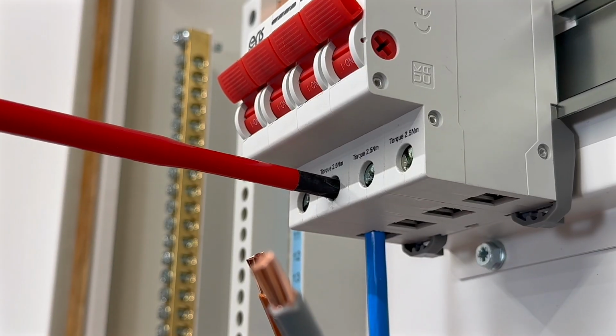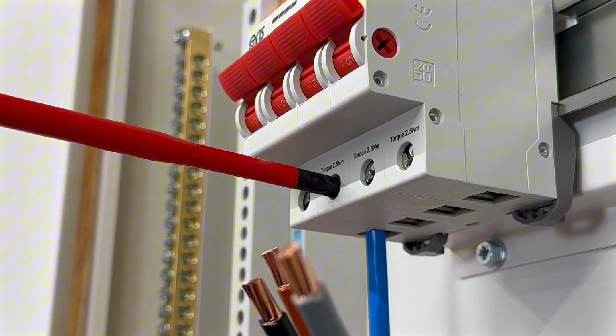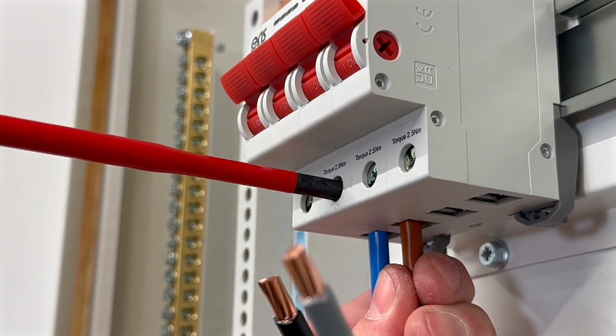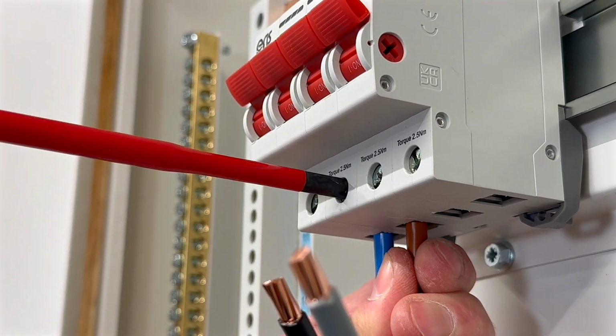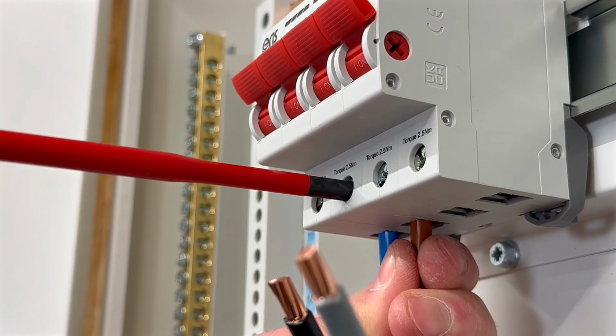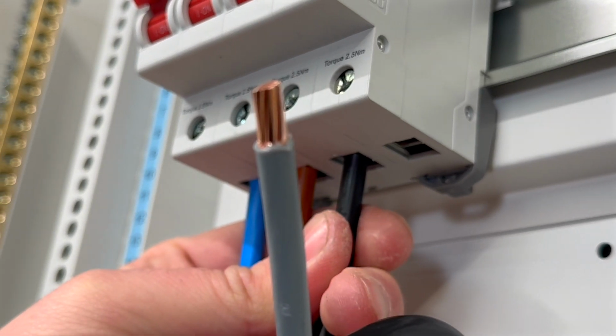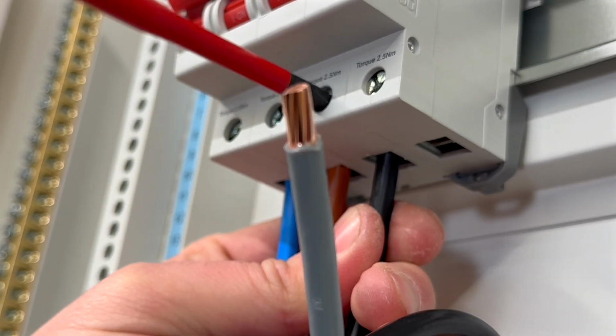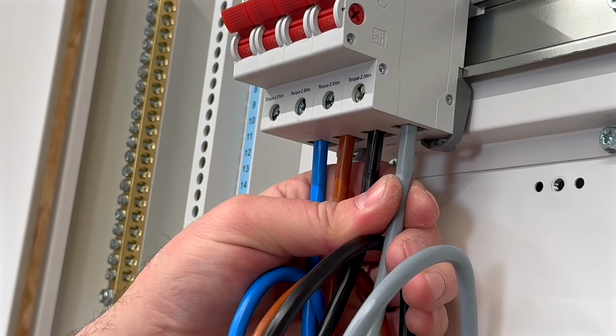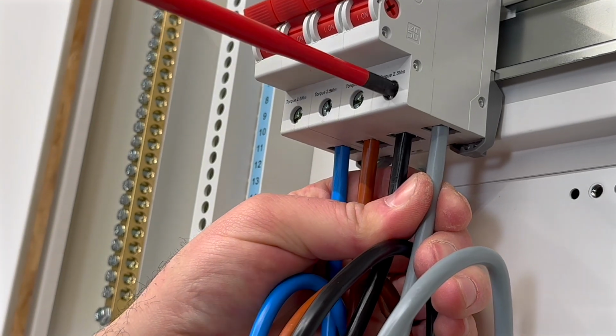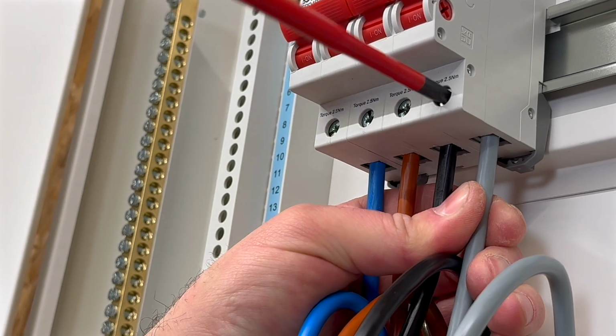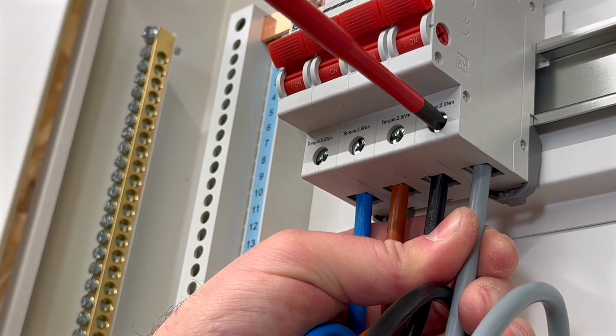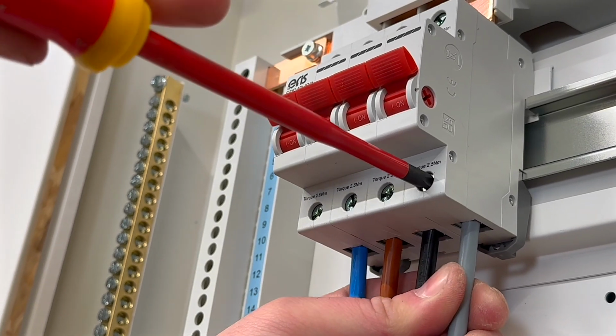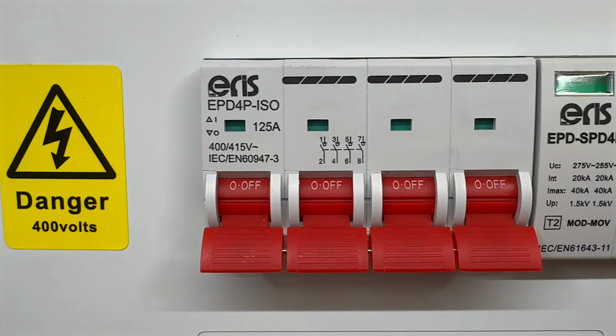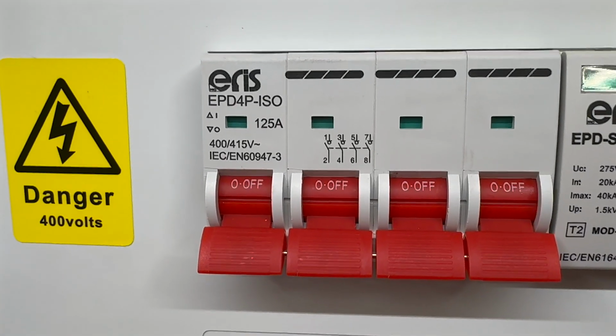At the input of the board, there is typically a main switch designed to disconnect all outgoing circuits. This switch may either be a 3-pole device disconnecting only the line conductors, or a 3-pole and neutral switch which disconnects all live conductors including the neutral. The choice of switch depends on the nature of the incoming supply and the designer's preferences. For more details on this topic, we've created a separate video and you can find the link in the description. This Eris board has a rated current of 125 amps.